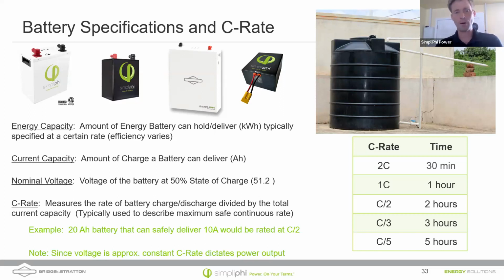Well, 200 amp hours, sure, that's the total capacity of the battery, but for lead acid, you would only discharge those batteries typically down to about 60%, maybe 50% state of charge if you're working them hard. So unlike lithium batteries, where you can discharge them all the way down to 0% state of charge without really doing much damage, with a lead acid battery, you could never do that. So one would be understanding how much capacity you actually need, right? Typically, you're going to get much more usable capacity out of a lithium battery.